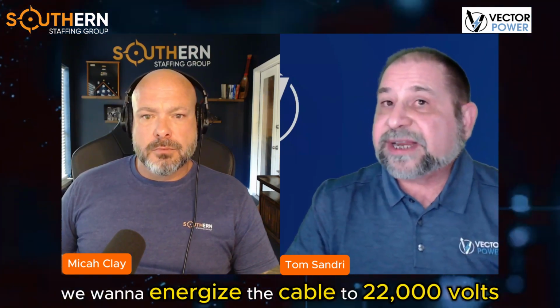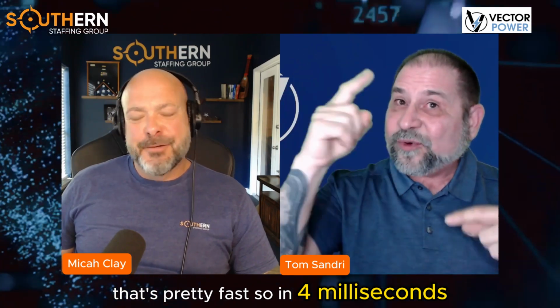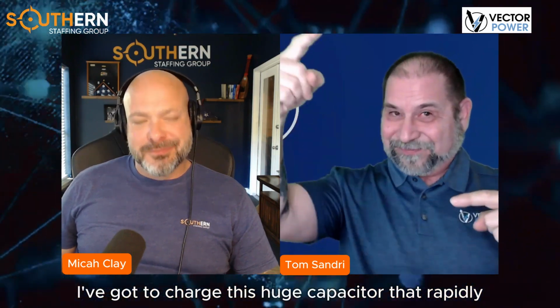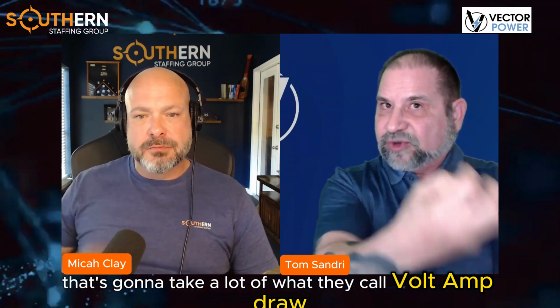Now remember, at power frequency, let's just say we want to energize the cable to 22,000 volts. I've got to go from 0 to 22,000 volts in about 4 milliseconds. That's pretty fast. So in 4 milliseconds, I've got to charge this huge capacitor rapidly. Well, that's going to take a lot of what they call volt-amp draw off of your power supply. So the VA size of the power supply gets very, very large.